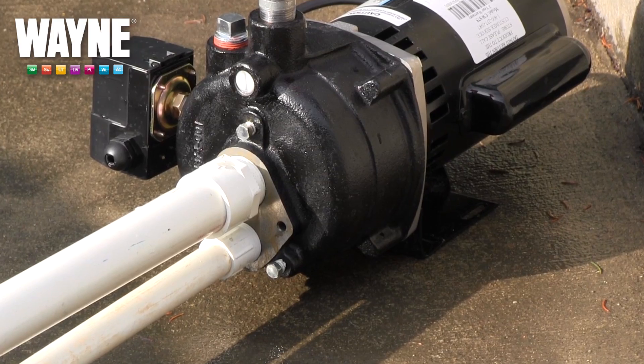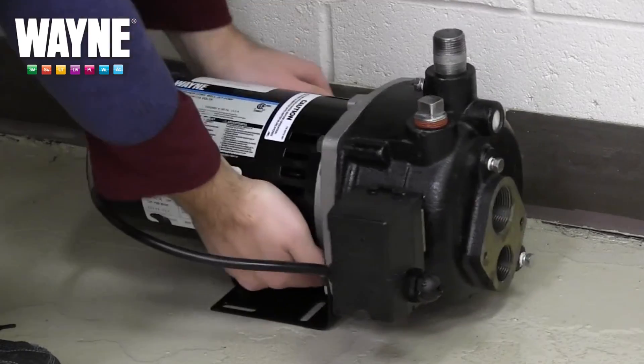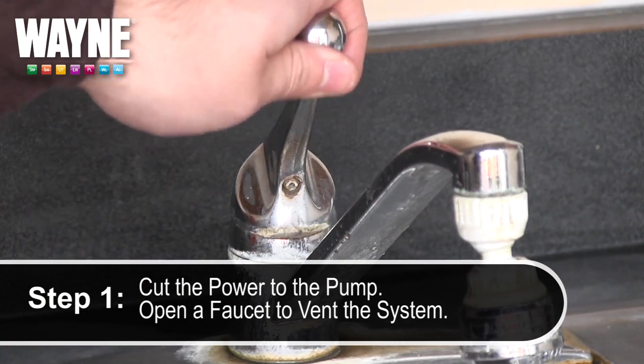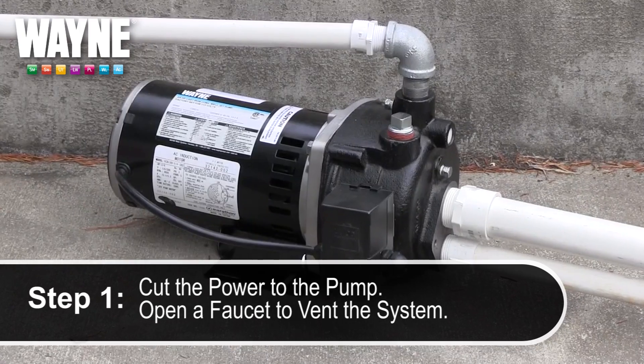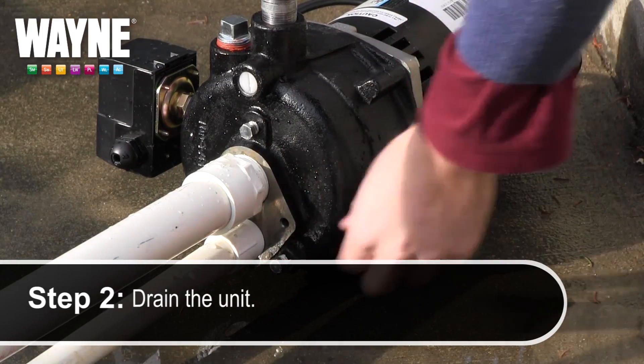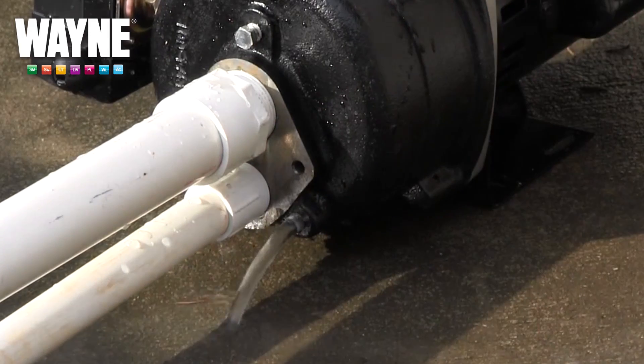To keep an idle pump from freezing in the winter, the pump must be drained or moved to a freeze-protected location. Begin by turning off the pump and opening a faucet on the discharge line to drain water and relieve pressure from the system. You can then drain the unit by unscrewing the drain plug and allowing as much water to escape as possible.